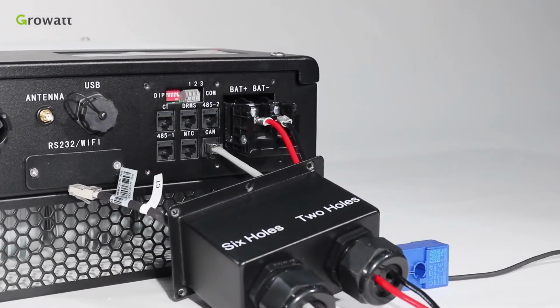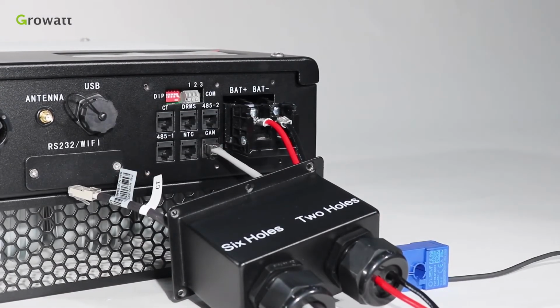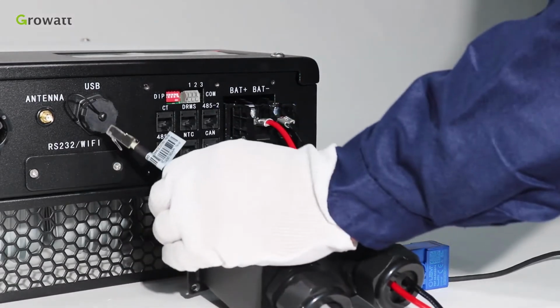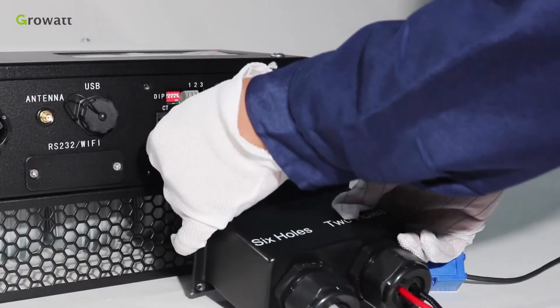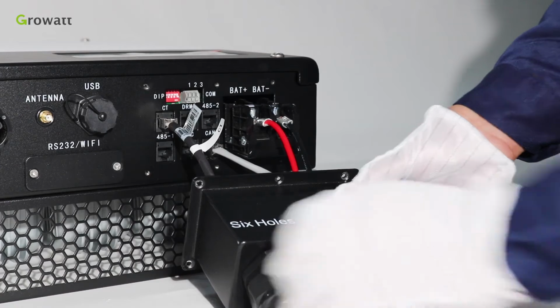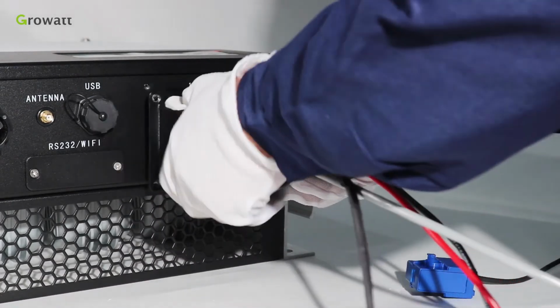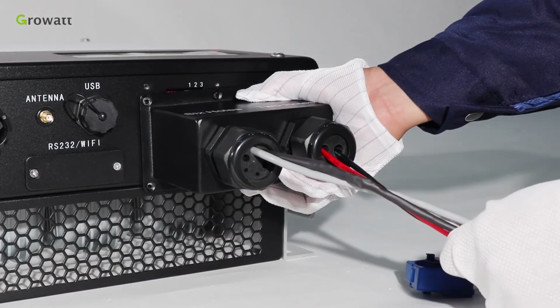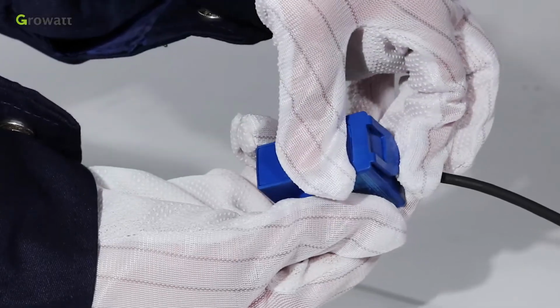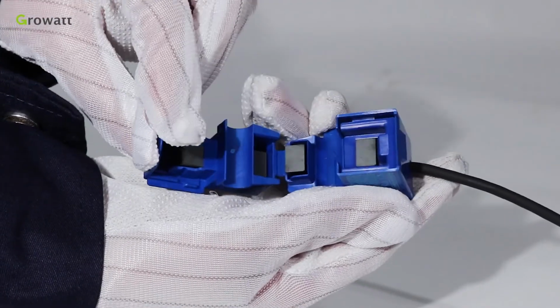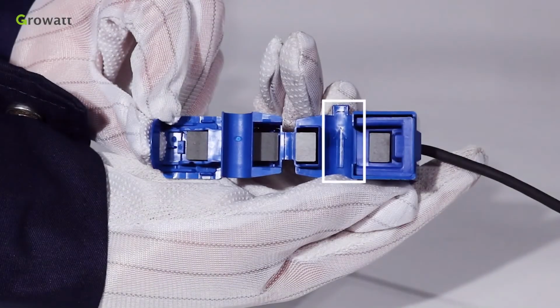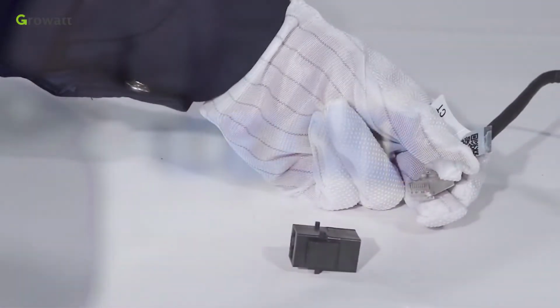larger than 5 AWG. For communication connection, thread the CT and battery communication cables into the waterproof cover as well. Connect them into the corresponding terminal and connect the waterproof cover into the inverter finally. Pay attention to the direction of the CT as illustrated. Open the current transformer and you can see an arrow labeled on it which indicates the current direction, and the direction of the arrow means from public grid to user load.